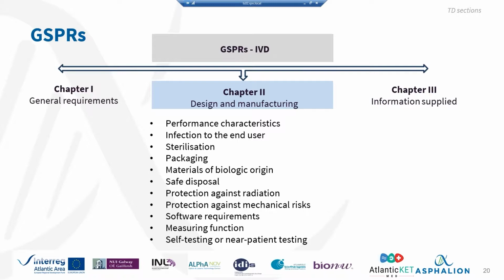So as you see, there are many points that have to be addressed, in particular depending on your device. So it's a quite important exercise to be able to identify which requirements are applicable to your device early on, so as to be able to test as much as you can before performing the technical documentation compilation.